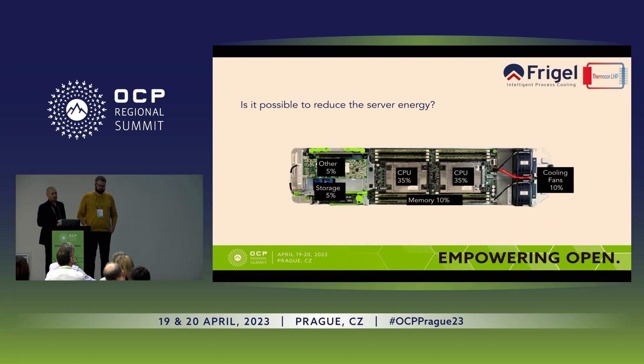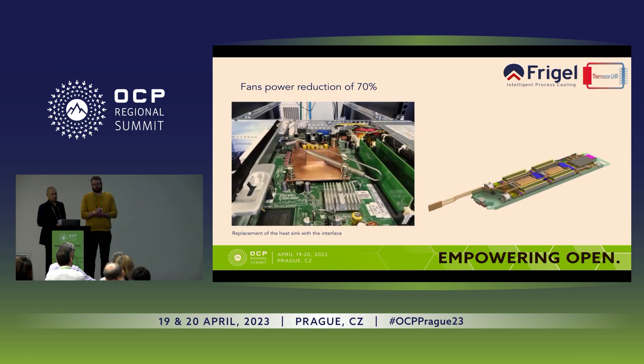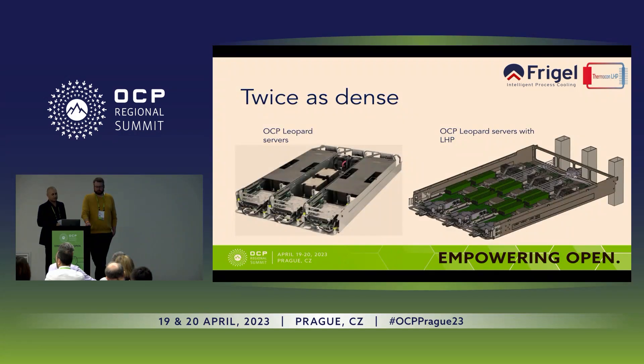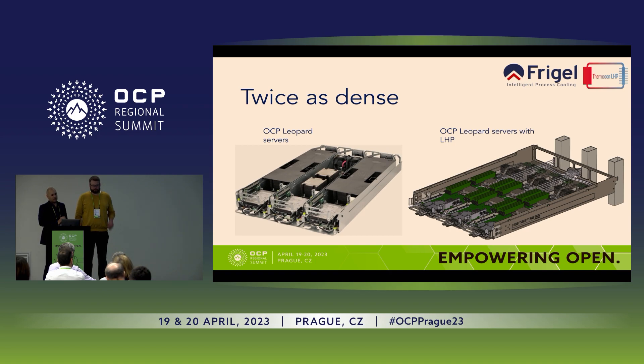Can we reduce the energy consumption of the server? Yes, we can — if we take away the heat from the CPU by liquid cooling. In that case, the fan power will reduce by 70%. Overall on the server, it will make an impact of just 7%, but it is significant. With OCP servers, instead of 3 servers with big heat sinks, we can shift to low-profile and place 6 servers instead of 3.